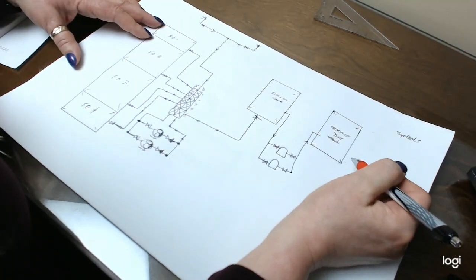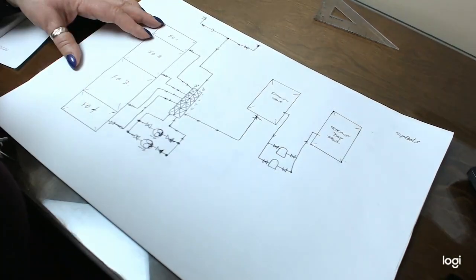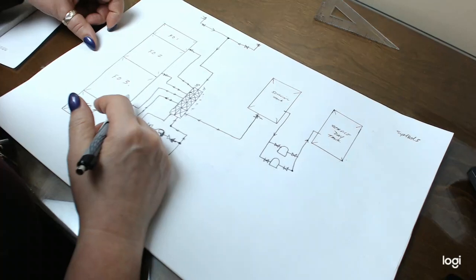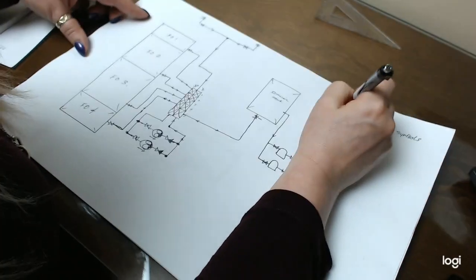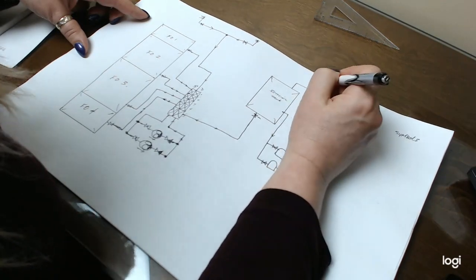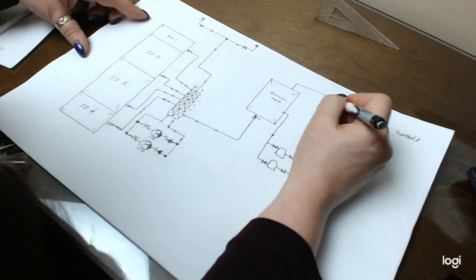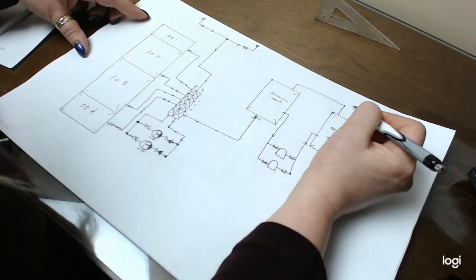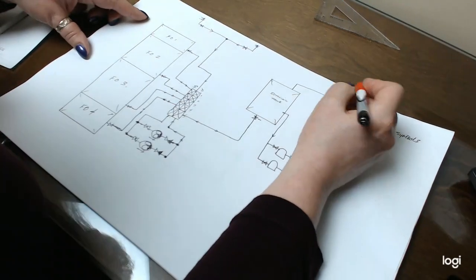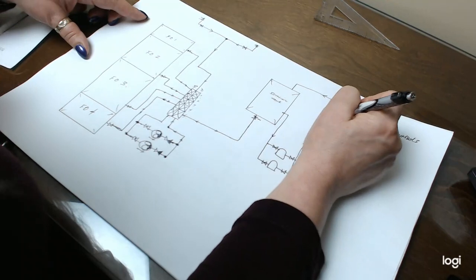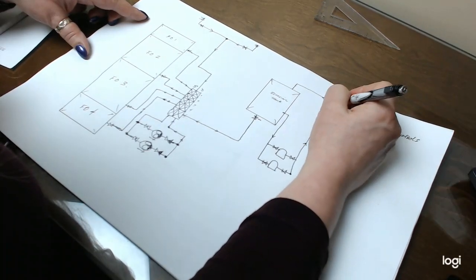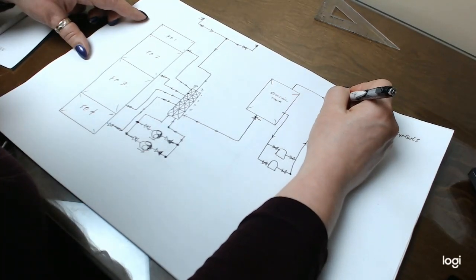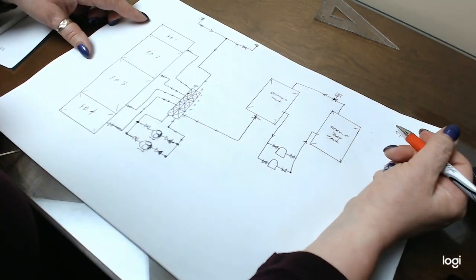If you fill up your service tank and you were afraid that it was going to overflow, one of the places you would design an overflow pipe is up here so that any fuel could flow directly back into the settling tank. This would give this direction. Sometimes there's a check valve on this, so I'm going to put a check valve on it so that it can't go back that way. And normally there's an alarm on that as well, but that's another separate setup.